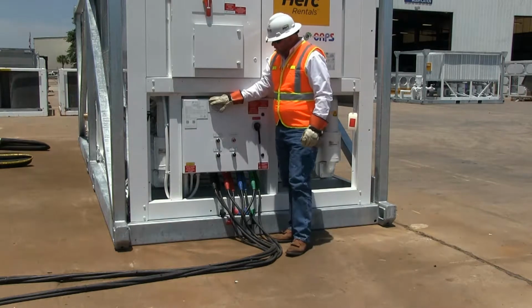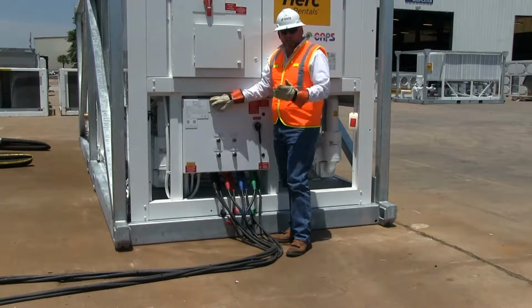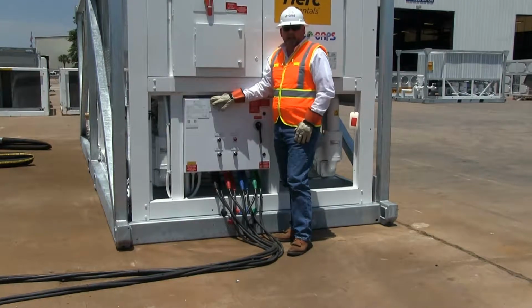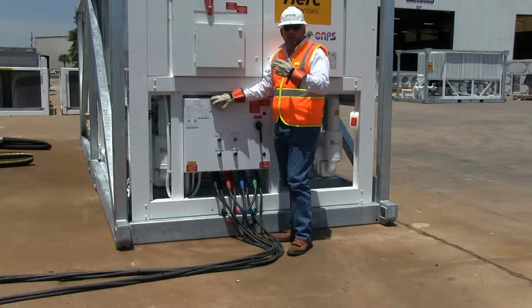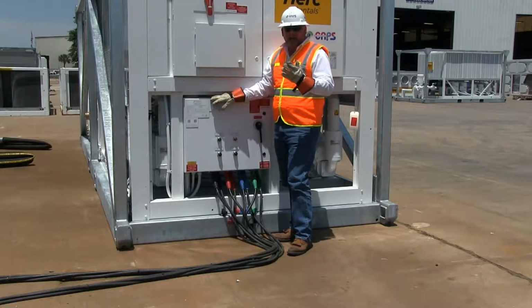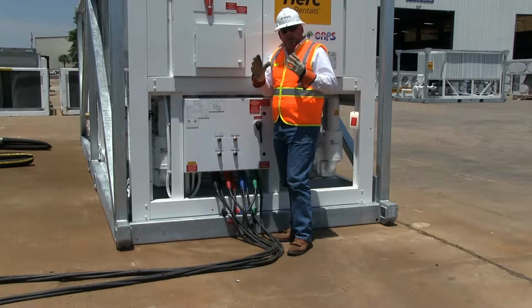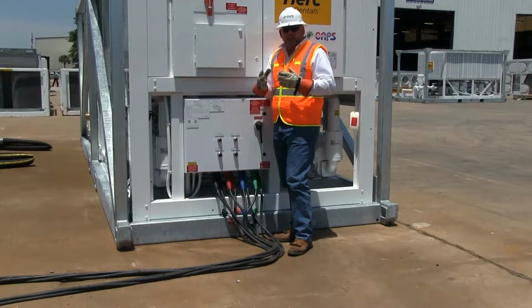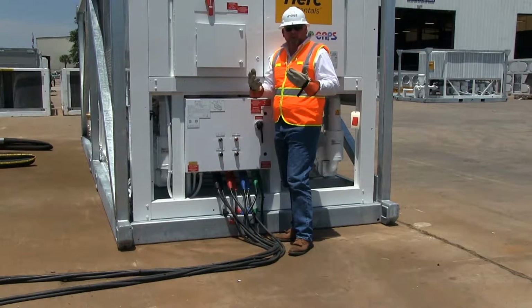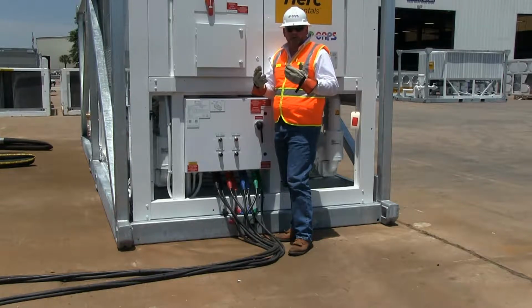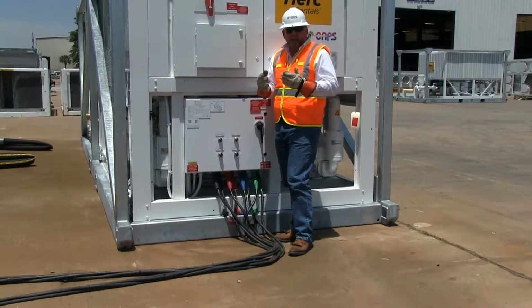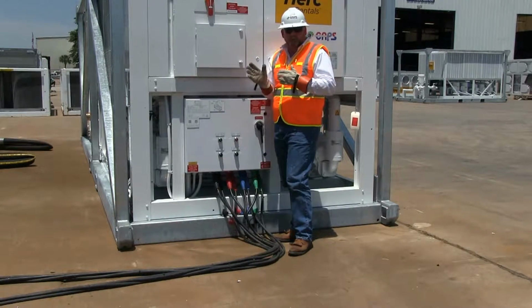Inside this pump panel is a lockout timer for this chiller. The purpose of that lockout timer is to have the 460 volt applied to the machine, lock it out for 1 hour to allow the compressor crankcases to heat up, heat the oil up, removing the refrigerant that might be inside the compressor so that we don't have a cold start. And that lockout timer will prevent the machine from running.